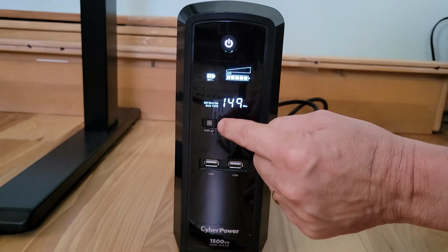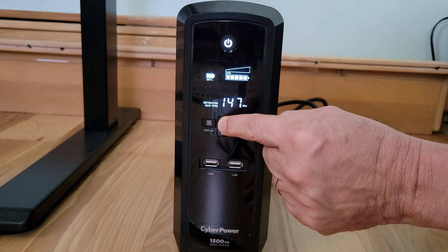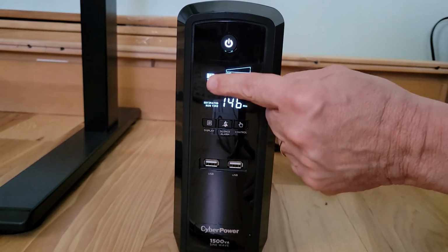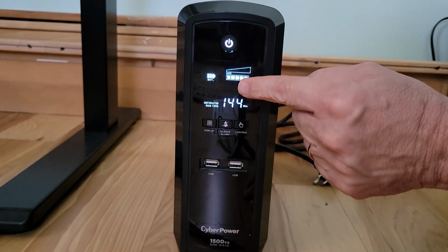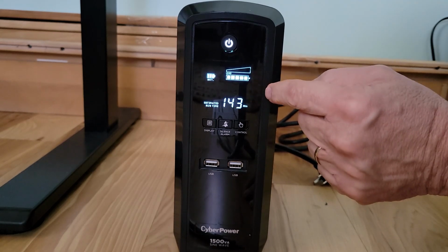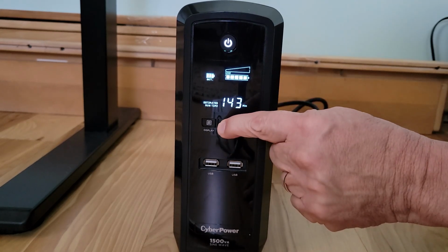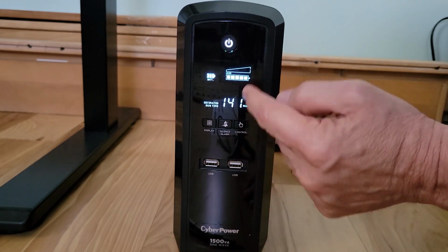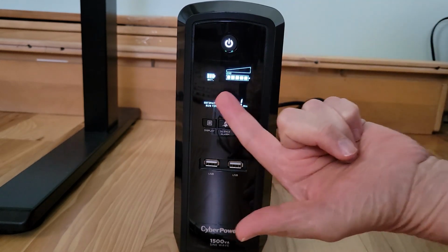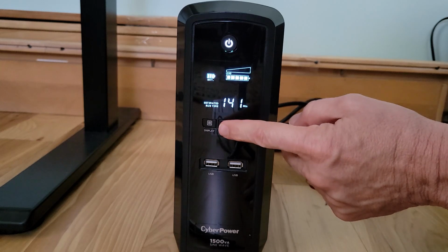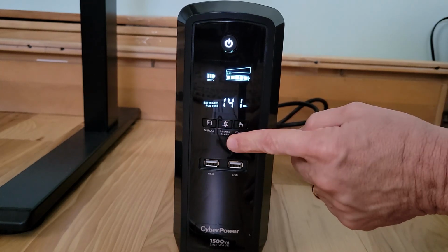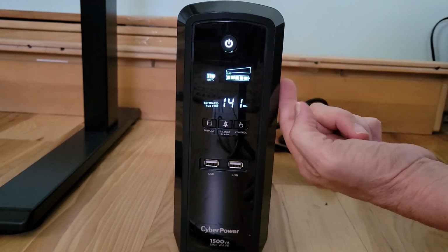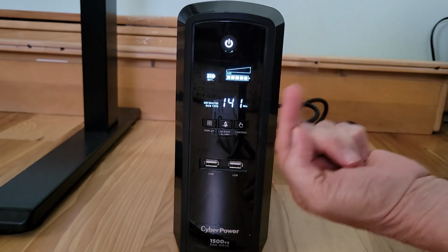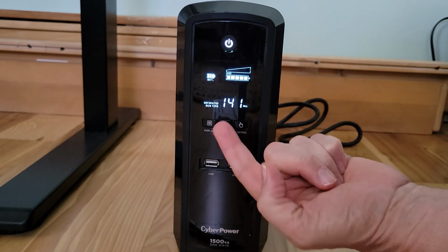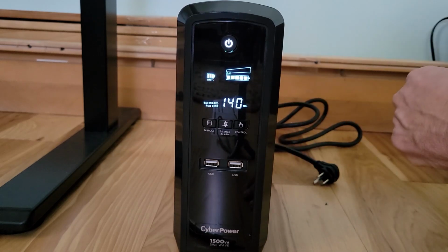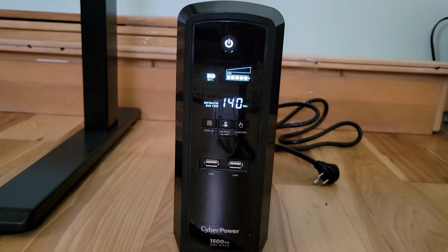So it would seem that this button is not working, because pressing it should reveal a little bell with a slash going through it that lets you know that the alarm has been silenced, and then you can just toggle that back on. But as you hear and see, that is not the case. So I'll see a little bit later, when we hook this up to the computer, if we can actually turn it on internally and bypass this button, which doesn't seem to be working. So let me plug back in the UPS.